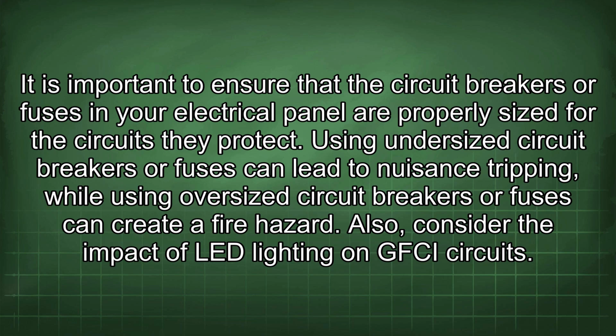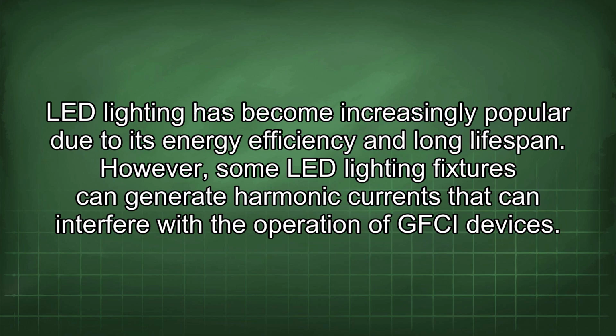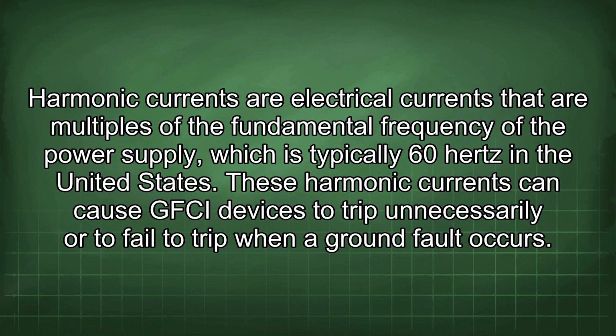Also consider the impact of LED lighting on GFCI circuits. LED lighting has become increasingly popular due to its energy efficiency and long lifespan. However, some LED lighting fixtures can generate harmonic currents that can interfere with the operation of GFCI devices. Harmonic currents are electrical currents that are multiples of the fundamental frequency of the power supply, which is typically 60 Hz in the United States. These harmonic currents can cause GFCI devices to trip unnecessarily or to fail to trip when a ground fault occurs.